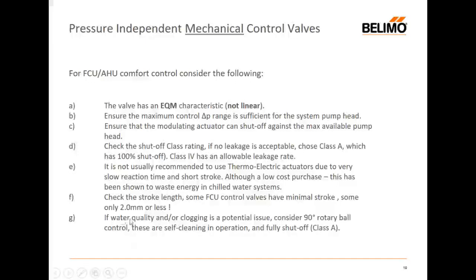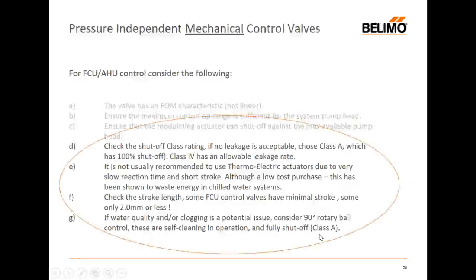particularly if there's an issue about aging systems where you might get a degradation of water quality or there's potential for clogging, then it might be worth considering a rotary ball valve, because they are self-cleaning, unlike the push-pull, and of course they will shut off at class A. But if you're happy with an allowable leakage rate, by all means, go for class 4, but then we're into push-pull and we're not closing off 100%.